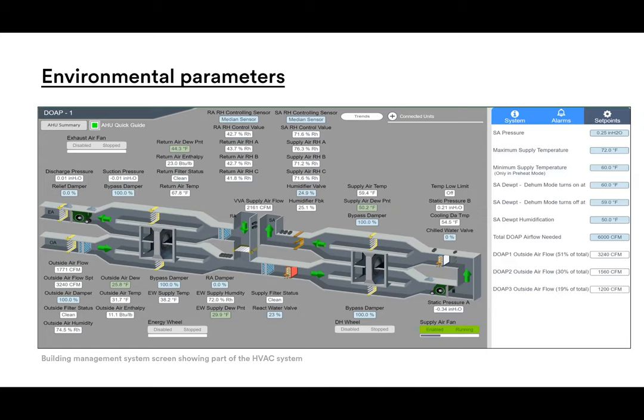When it comes to our art collection, we know that it's not the actual temperature or humidity that can present a problem, it's actually the rate at which these parameters change that can be the most harmful. Of course, there's a maximum and a minimum that we must stay within, but if we stay within these higher and lower limits and keep our rate of change very slow, we can in fact move our humidity and temperature set points to match the season and subsequently save quite a lot of energy.